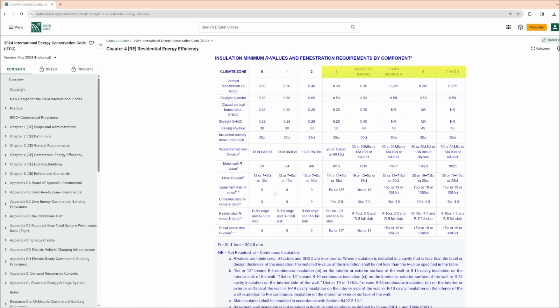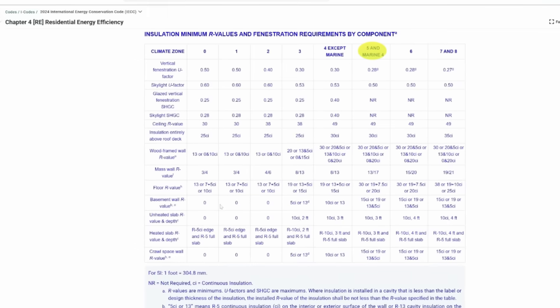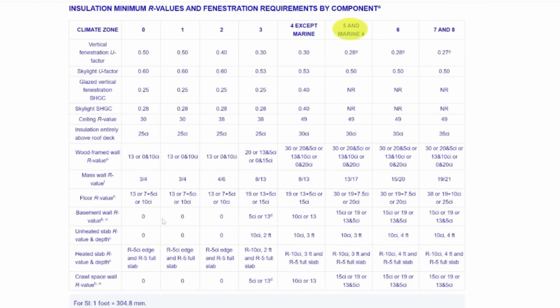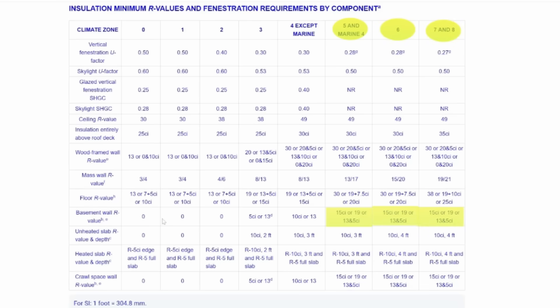Now, this is where we can run into some problems. If you look at these numbers, you'll see that there are two or three figures that are thrown out. For example, if we go over to climate zone 5, we see a requirement for either R15 CI — that means R15 continuous insulation — R19 cavity insulation, or a combination of R13 cavity insulation plus R5 continuous insulation. And we see the same figures used for climate zones 6, 7, and 8.